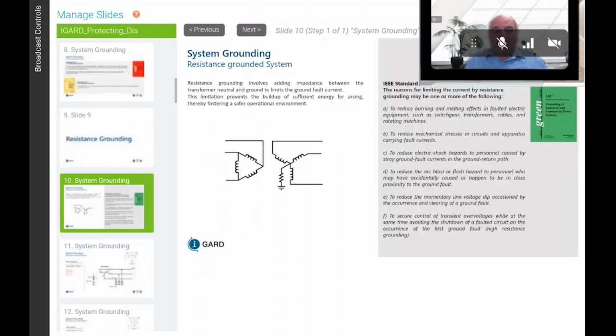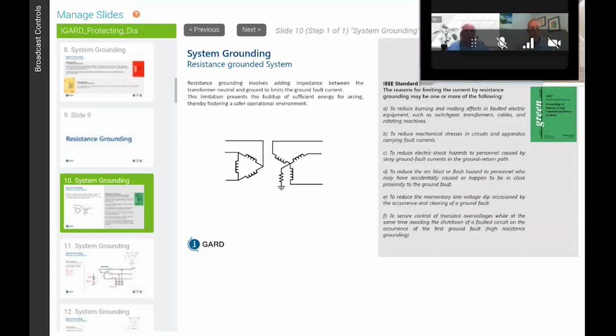This is why we go to resistance grounding. If you remember that transformer that we had originally with a solid link from the neutral point to ground, we replaced that with a resistor. If you replace it with the resistor, your entire secondary of the transformer is protected as if it were a high resistance grounded system. So 250.36 in the NEC and 10-300 of the CEC state that if you have a resistance grounded system and you limit the fault current to a low value, in Canada, up to 4160 volts and less than 10 amps, you don't have to trip. In the US, the NEC states that if you limit the fault current to a low value, less than 1000 volts, you have a high resistance grounded system and you don't have to trip.